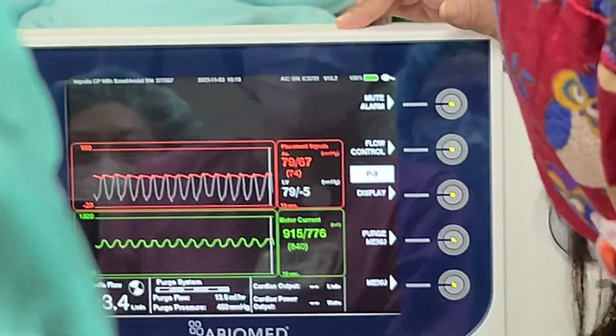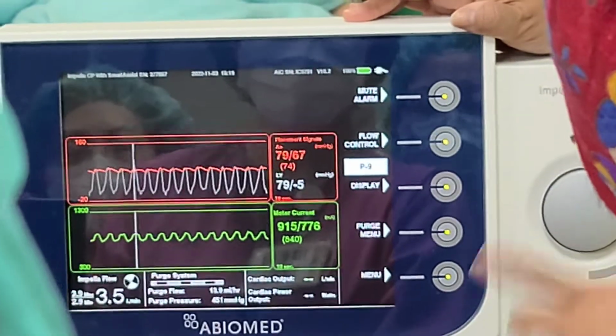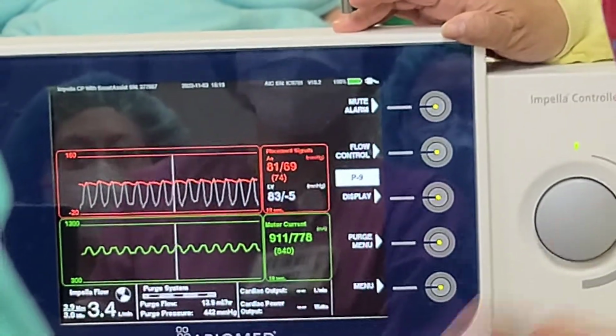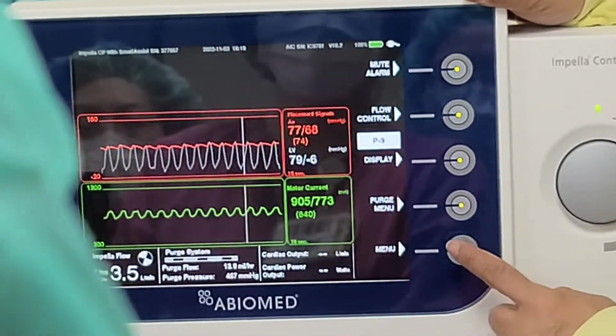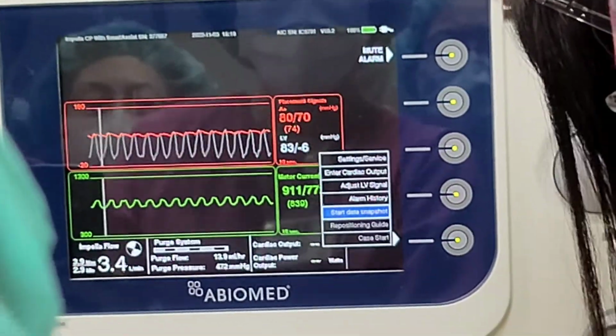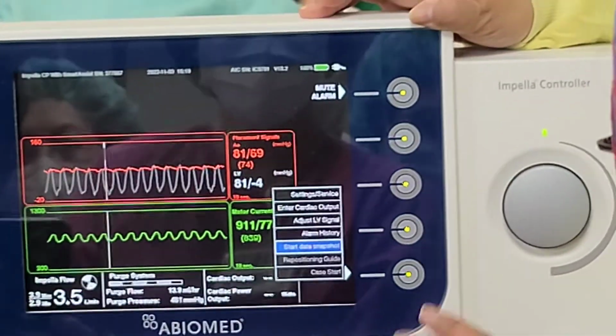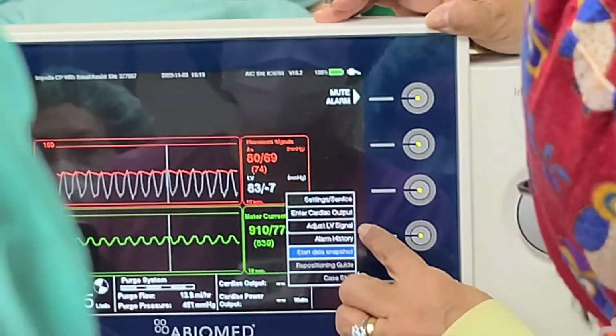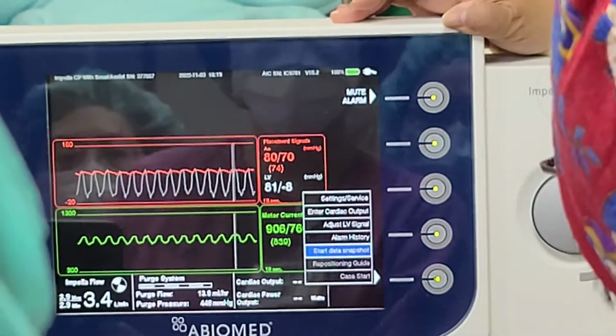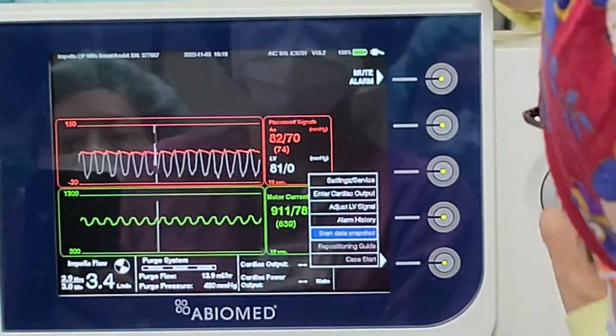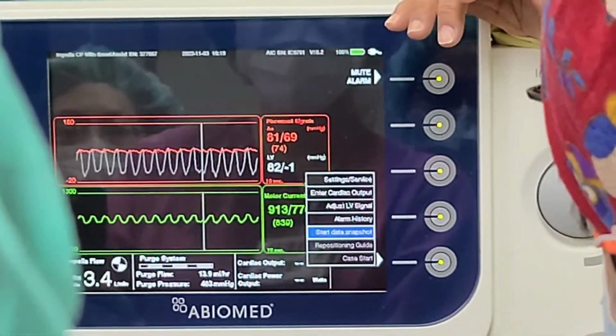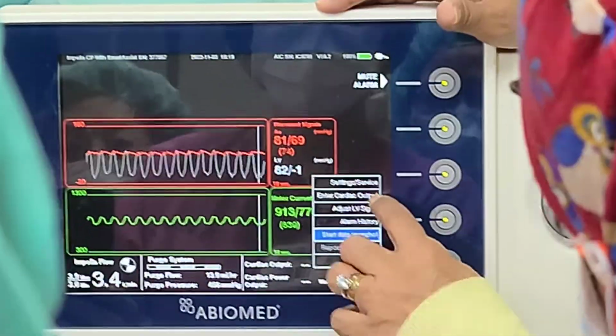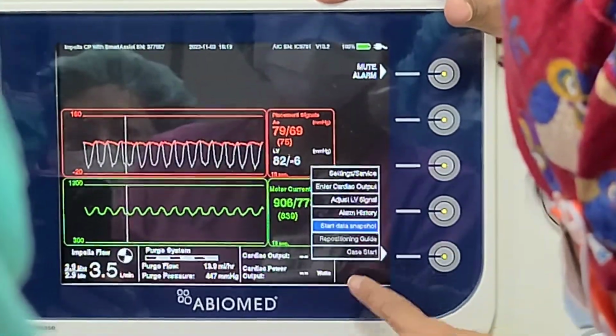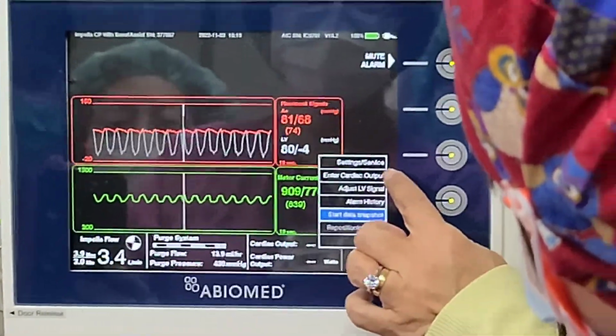Menu is when you want to do something, you want to make a change, you want to enter something. So if you go to menu, you can look at alarm history, which you don't need to do. You can adjust LV signal, you don't need to do that - you only do it if the alarm comes out to tell you to do it. The machine is very clever, it will tell you when you need to do something. And then enter cardiac output - if you want to enter the cardiac output, that's where you will go. And then settings and service, which you do not go to.